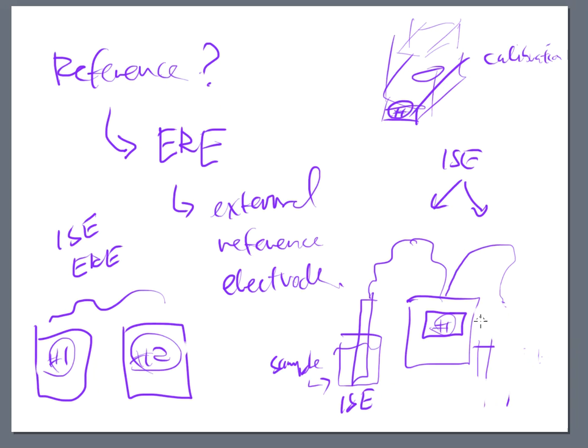So what that means is that those two components, again, think of two containers in a galvanic cell, have now been combined into one. And this is called a combined electrode. That's what that is. So in modern day pH meters, that probe does have two containers, like a galvanic cell. There is an ISE on the inside of that probe, and there is an ERE on the inside of that probe. They're all designed this way pretty much now. It's very convenient. It's cheap to make. The science has been there for years. We don't really expect anything any different than that combined probe or that combined electrode.